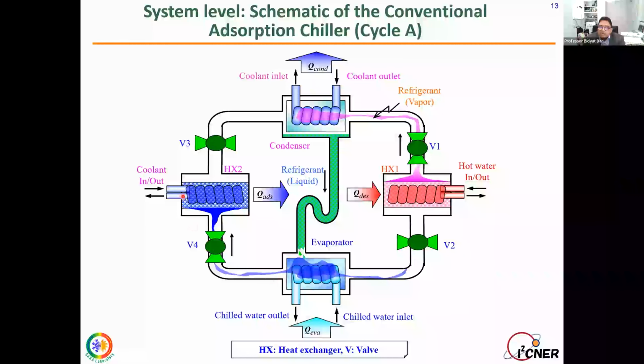What happens here is that after some minutes, like 7 minutes, most of the water vapor and the silica gel bed are in a saturated condition. If I have 10 kilograms of silica gel in this heat exchanger, after 7 minutes about 3 kilograms of moisture can be adsorbed. So it is nearly saturated, and it is very difficult to adsorb more. In this sense, we have to change the operation mode of this cycle.